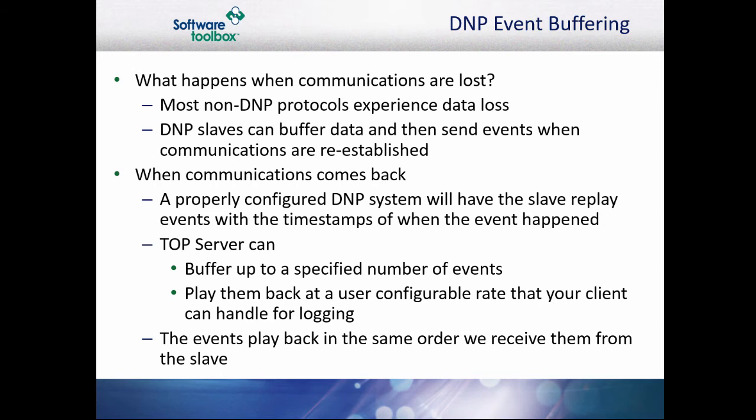So what happens when communications fail between the master and slave? Most of the time you would lose that data. However, DNP3 slaves can store event data for each point and then send the data when communications are re-established. Your slave determines if it can buffer, how much data it can buffer, and all other buffering settings. Configuration of these slave hardware settings is outside the scope of our support.